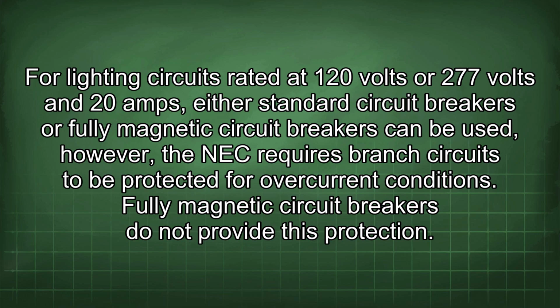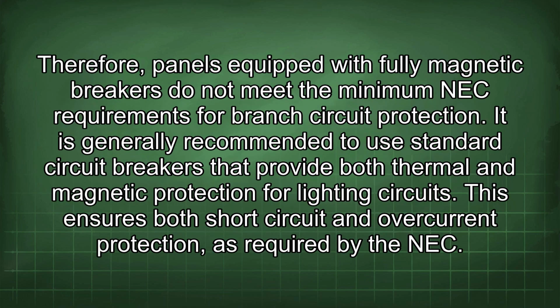For lighting circuits rated at 120 volts or 277 volts and 20 amps, either standard circuit breakers or fully magnetic circuit breakers can be used. However, the NEC requires branch circuits to be protected for overcurrent conditions. Fully magnetic circuit breakers do not provide this protection. Therefore, panels equipped with fully magnetic breakers do not meet the minimum NEC requirements for branch circuit protection.